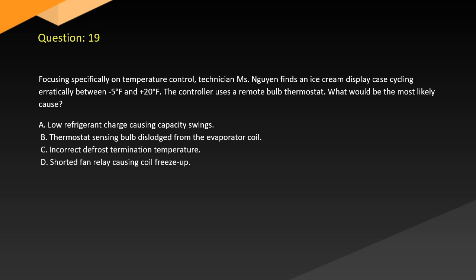Question 19. Focusing specifically on temperature control, a technician is new and finds an ice cream display case cycling erratically between -5 degrees and +20 degrees. The controller uses a remote bulb thermostat. What would be the most likely cause? A. Low refrigerant charge causing capacity swings. B. Thermostat sensing bulb dislodged from the evaporator coil. C. Incorrect defrost termination temperature. D. Shorted fan relay causing coil freeze up.